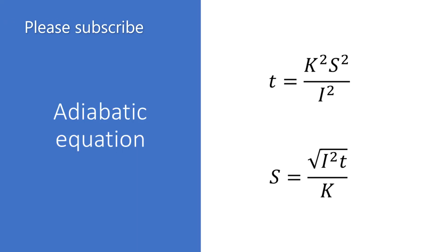The second thing is the adiabatic equation. To carry out the adiabatic equation we need to know the current and the time it will take to operate the protective device. So in the first equation T equals K squared multiplied by S squared divided by I squared is for the thermal withstand of the line conductor. And what we are looking for is for the time in seconds to be greater than the time that the short circuit current would cause the protective device to operate, which we can confirm by plotting the current on the time current characteristics.